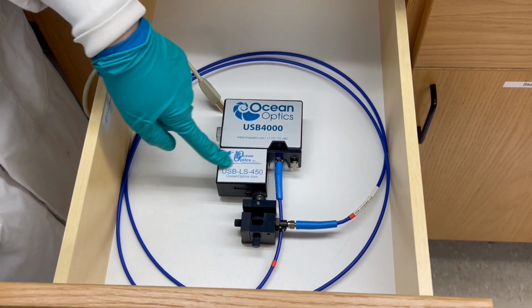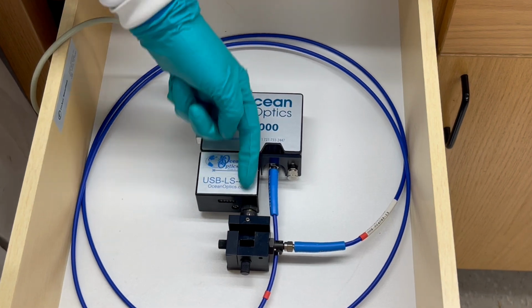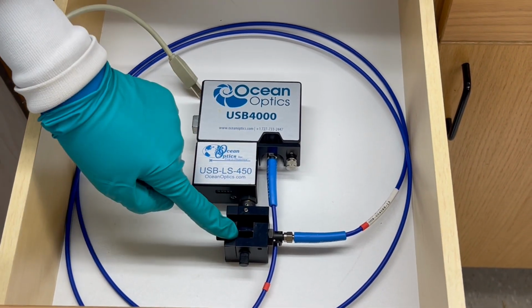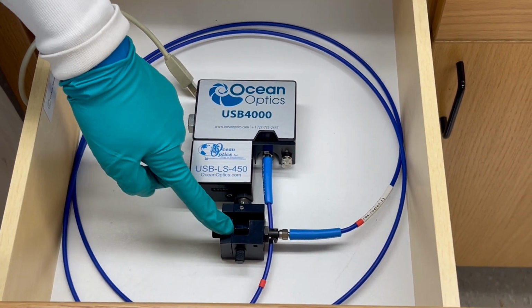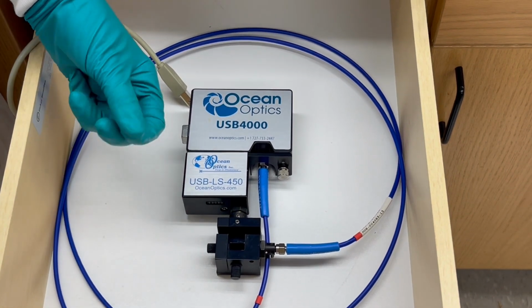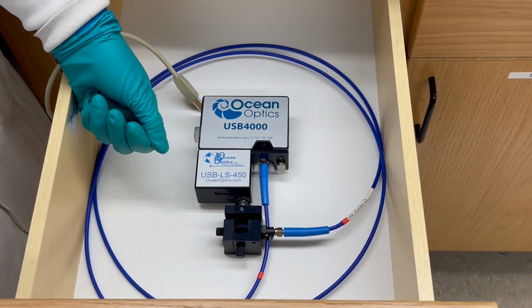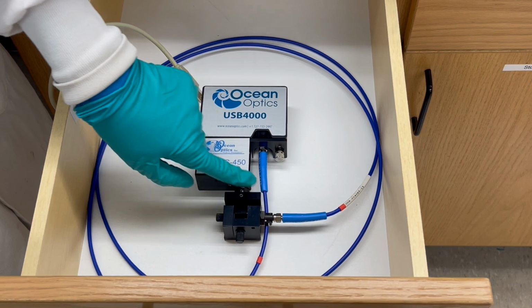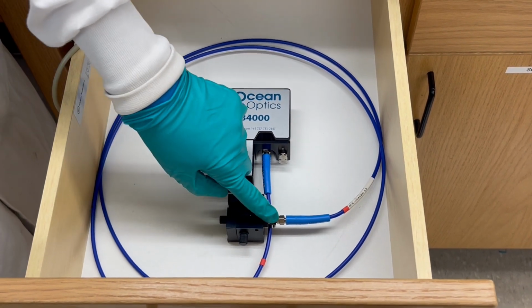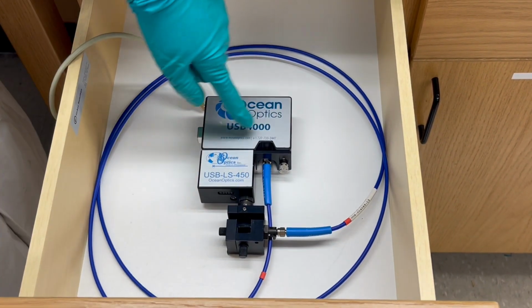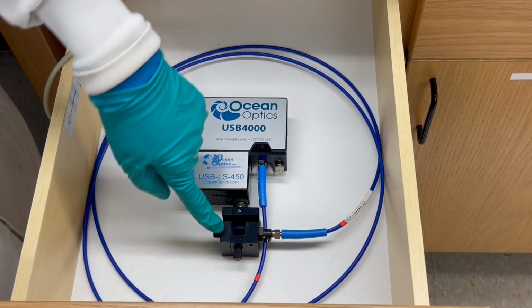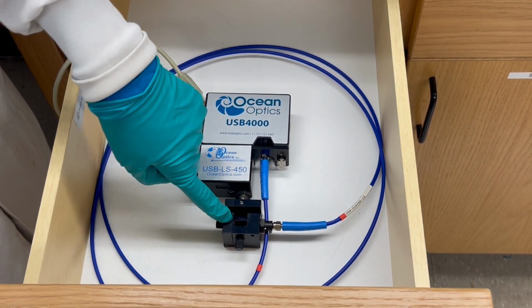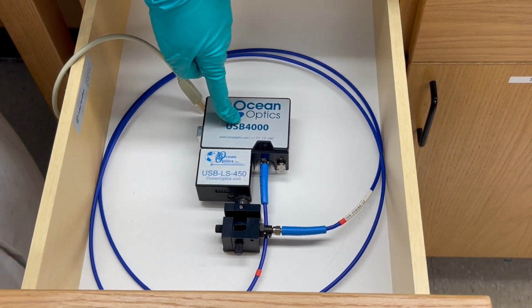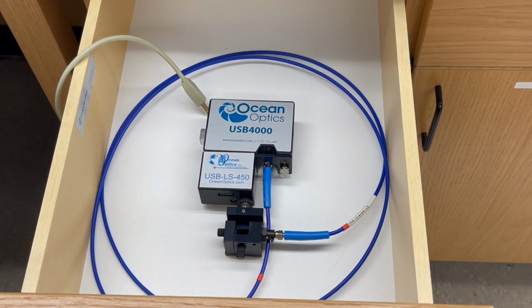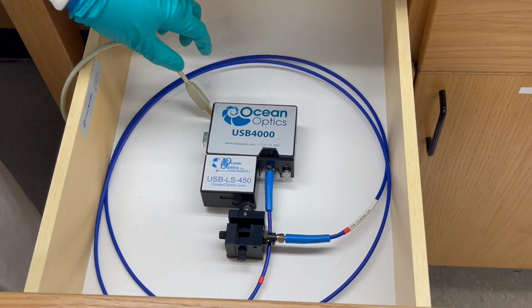The source is a monochromatic wavelength that's going to be going into a cuvette, which should be in this holder. And then fluorescence has your sample emitting light at a 90 degree angle to the incident light. So 90 degrees to the incoming light, we have a fiber optic cable that connects to your detector. All of the photons that are being emitted from your sample will be sent to the detector, which then will send that to the computer to show the spectrum on the screen.